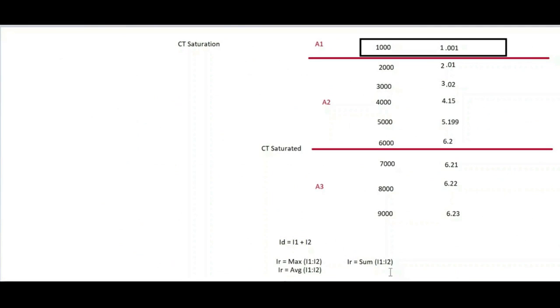Which formula we should use? That actually depends on the numerical relay. It is an inbuilt algorithm. So from this concept, what we understand is, because of the error in the CT, and that also the error is not working in the same way. It works in 3 different ways in 3 different regions.